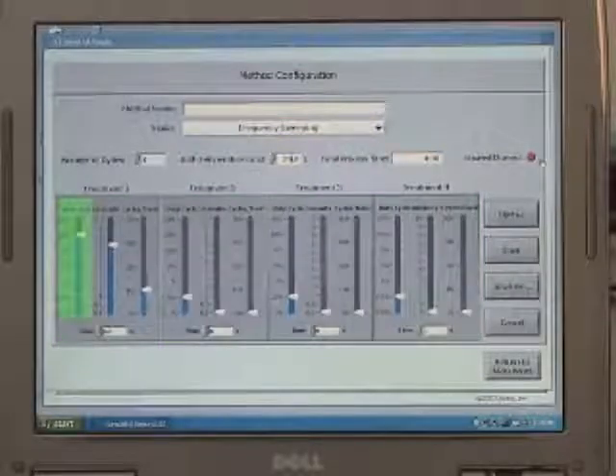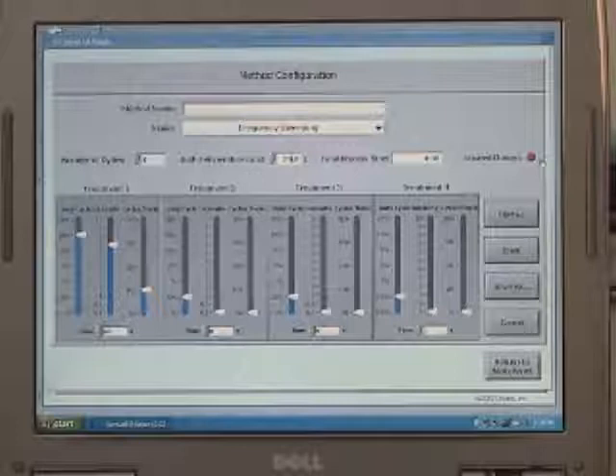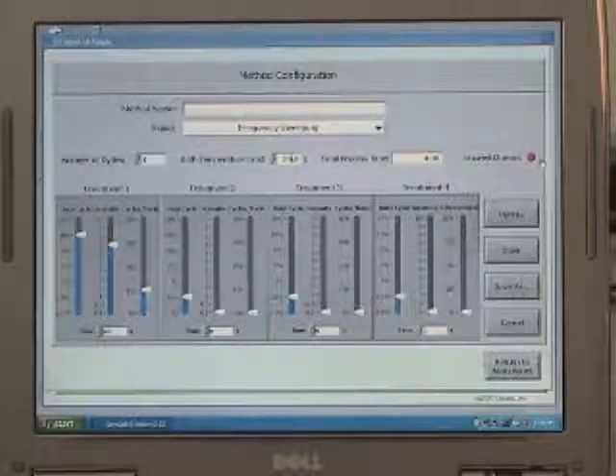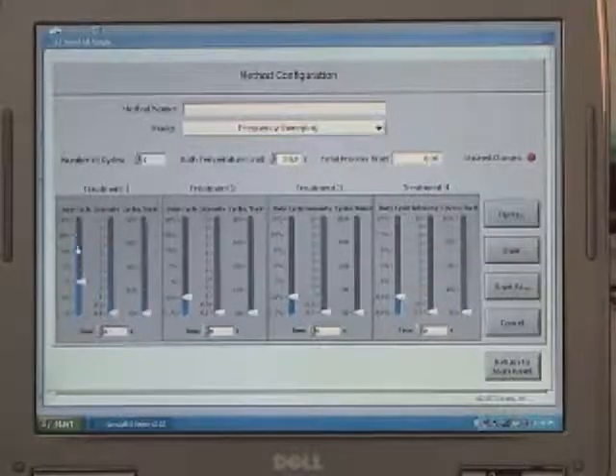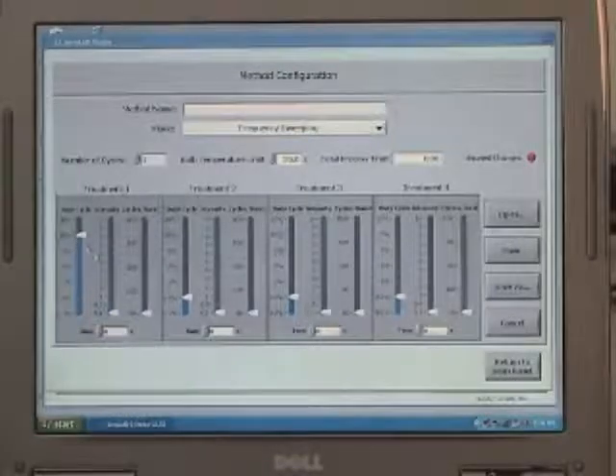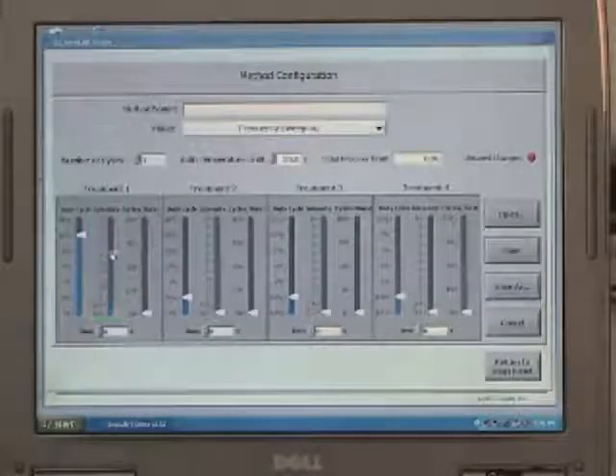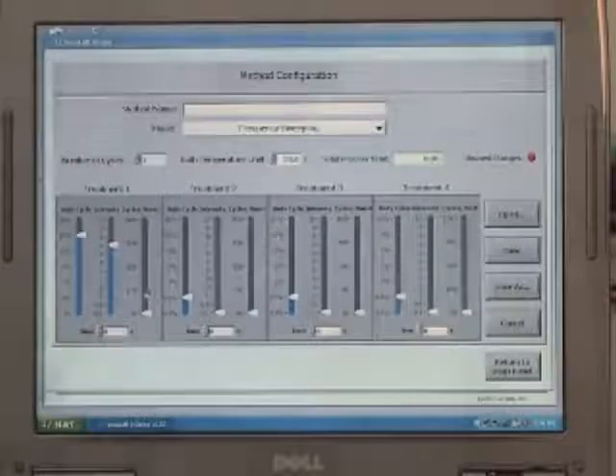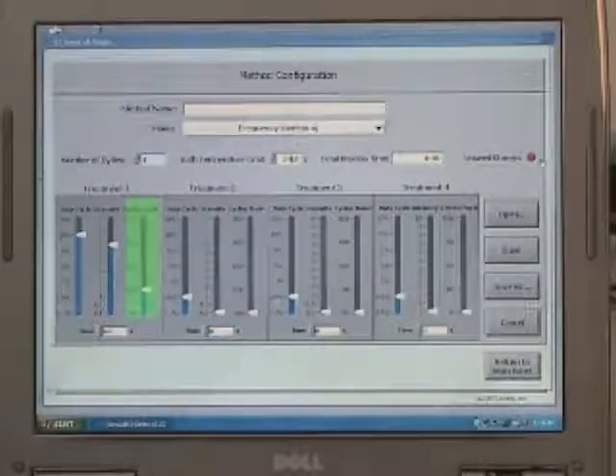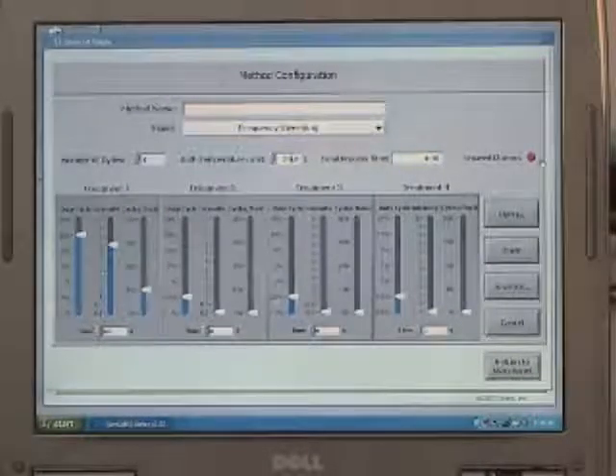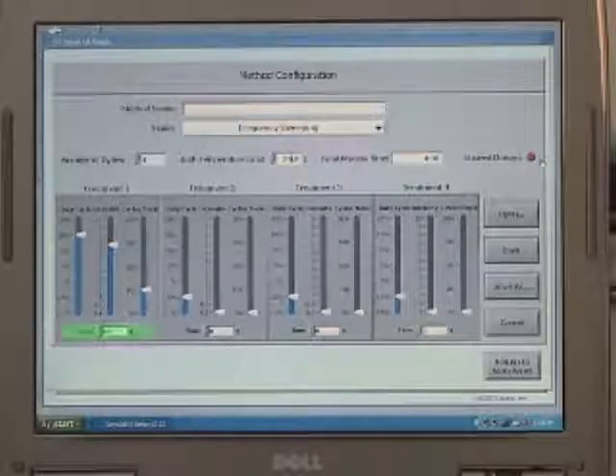Duty cycle is the percentage of time the transducer is generating acoustic waves. The values for all the acoustic parameters can be changed using the sliding bar next to the scale. Intensity is the amplitude of the pressure waves generated by the acoustic transducer. Cycles per burst is the number of waveforms generated by the transducer during an on period. Time is the length of time in seconds a treatment will run. The maximum is 60 seconds.